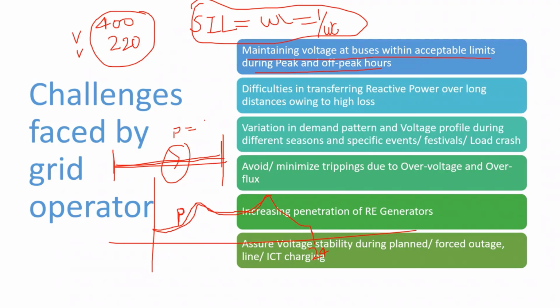However, if the line is loaded beyond surge impedance loading, the voltages will go down. And if it is loaded lower than surge impedance loading, then your voltages will go up throughout the transmission line. This kind of thing happens in the transmission system because the day-to-day power flow on the same line varies all the time, depending upon the load generation balance in the system, how much load is coming into the system and how much is going out. So this power flow always varies. When it varies, the reactive power generation and absorption by this transmission line will also vary.